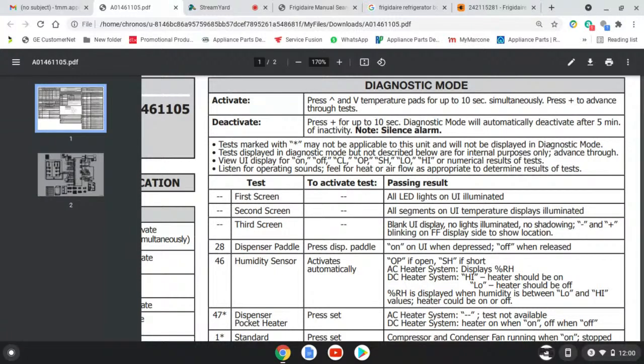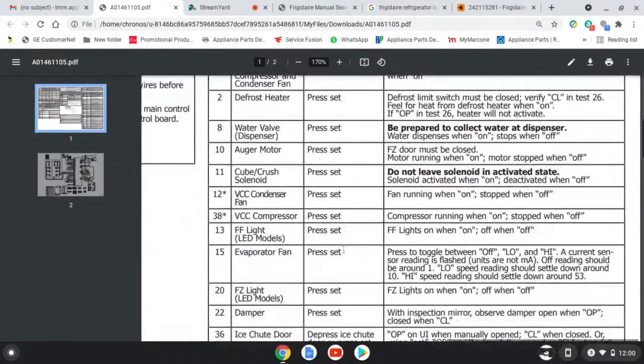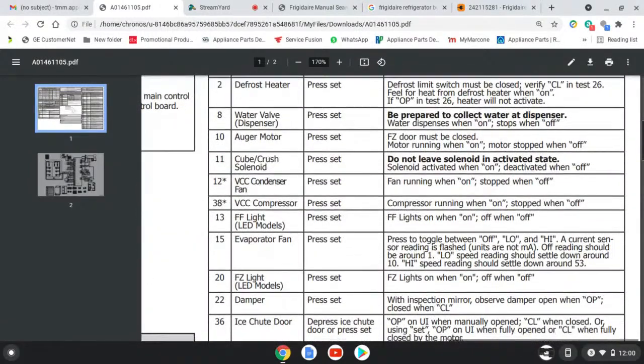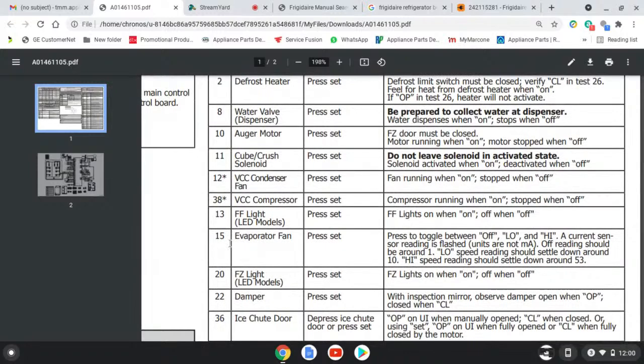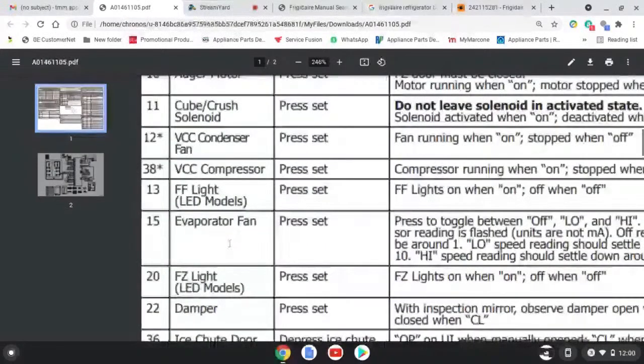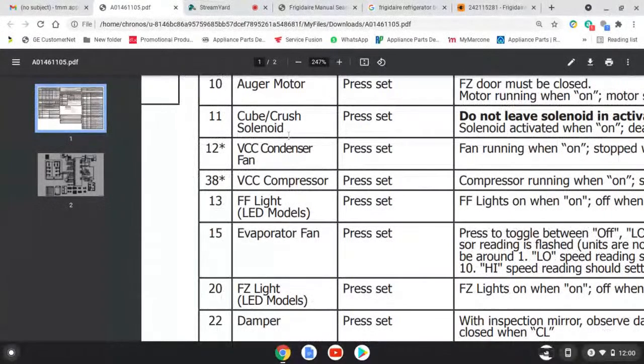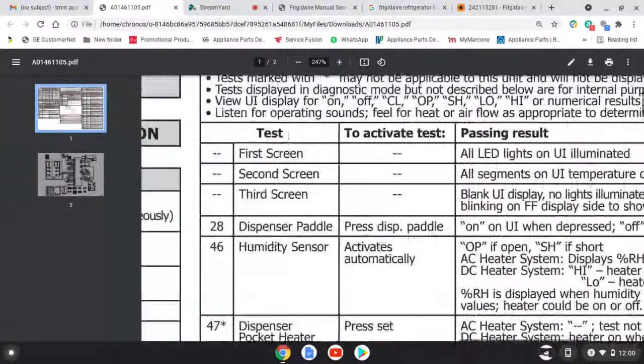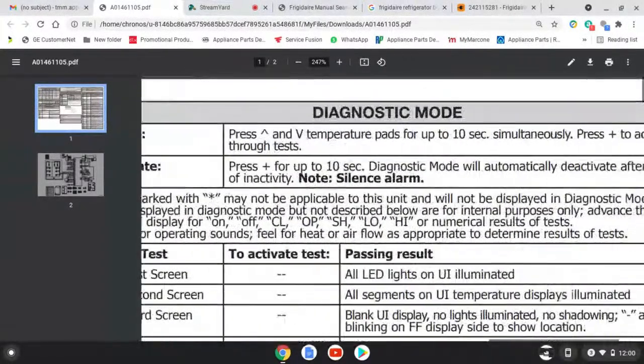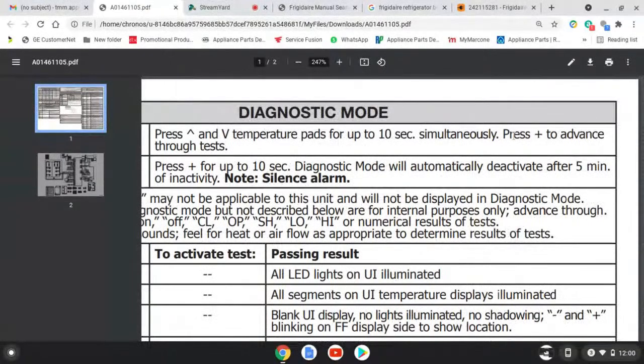Let's go down to that evaporator fan, because that's our culprit, that evaporator fan. Here it go right here, test 15. But we've got to advance to test 15. So how do we advance to that test? Press the plus button to advance through the test. Right there, come on, right there. Let's go ahead and do that till we get to 15.